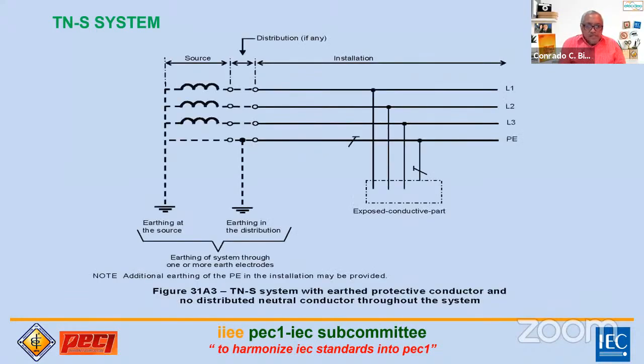Then meron tayong isa pang TN-S. Yung kanina, yung nauna, may tinatawag na distributed neutral. Dito, wala siyang distributed neutral sa low voltage installation. Same transformer, ang source, meron tayong distribution system dito, then meron tayong installation. Makikita mo, protective earth lang ang ginamit, so wala kang connection sa neutral kahit anong load.